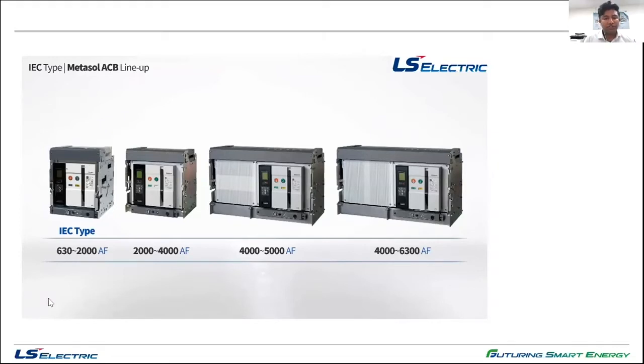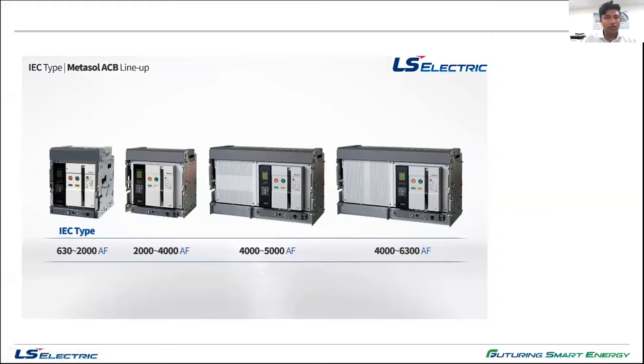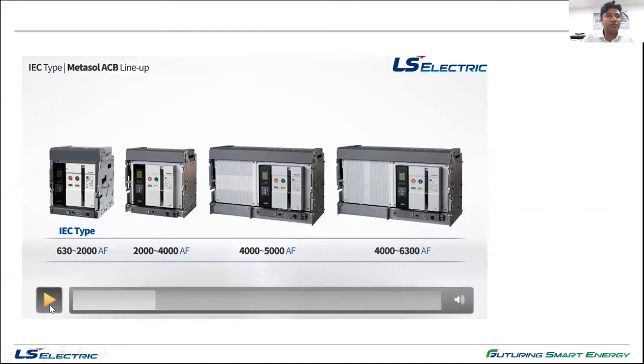The second frame size, which is up to 4000 amps, we call it the E frame. So generally how we represent the frames is D frame, E frame, F frame, and G frame. If you register that in your mind, our selection of breakers and selection of cradle will be very easy. So always note that in LS, the frame sizes are D frame, E frame, F frame, and G frame. Now coming to the E frame, it is already 85 kA at 500 volt, which I believe is more than sufficient in this market.